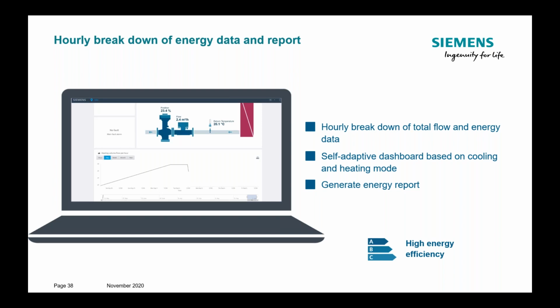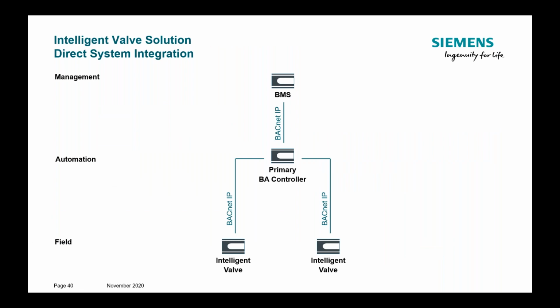Nevertheless, this is a network device. These intelligent valves are network devices, so they can be integrated into the building management system and the building automation network as well by BACnet, by Modbus, on the level you need. We prefer BACnet IP because that's the most powerful and easiest from our point of view to commission together with the primary controllers. There you have the full transparency and the most performance out of this.